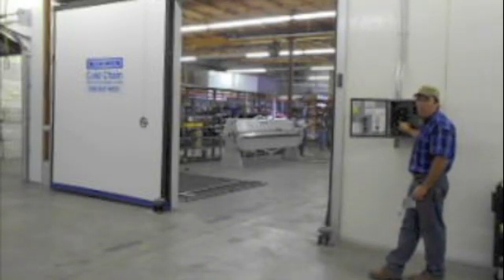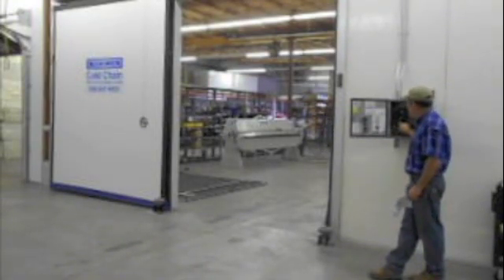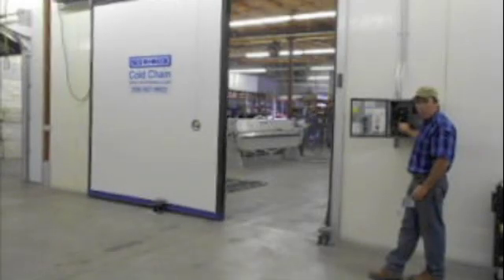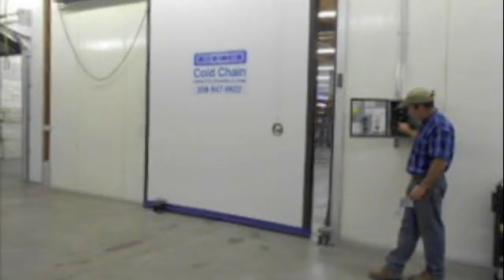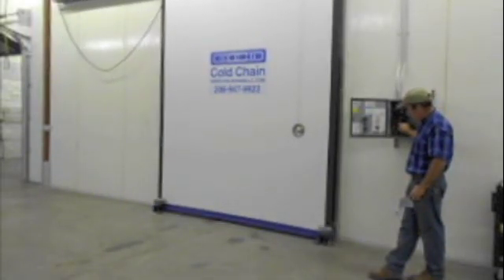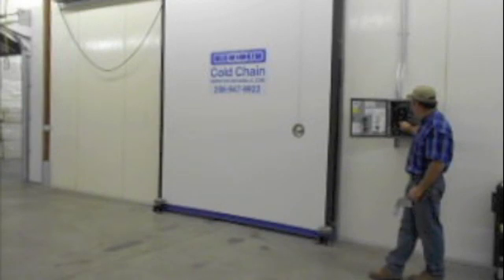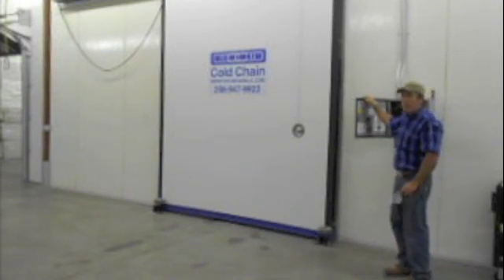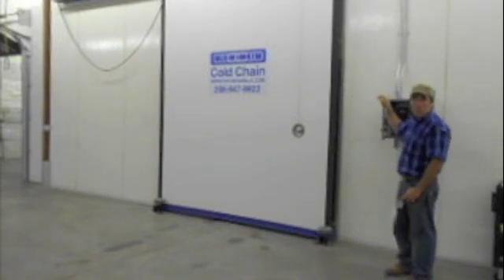Then it will say 'status, jog door close.' Press the down button until the door is fully closed. Once it's closed to where you want it to seal good, press enter.